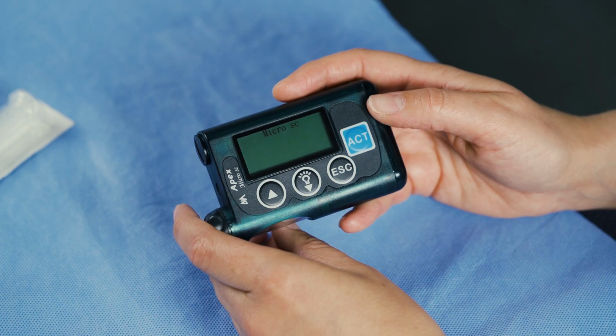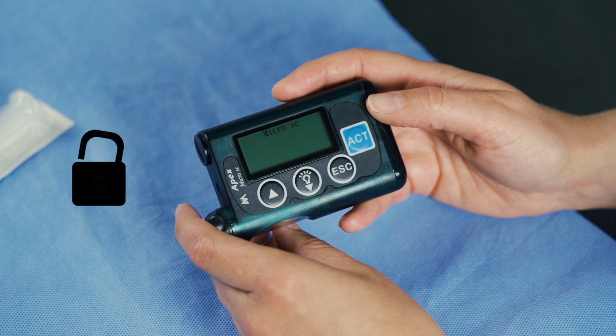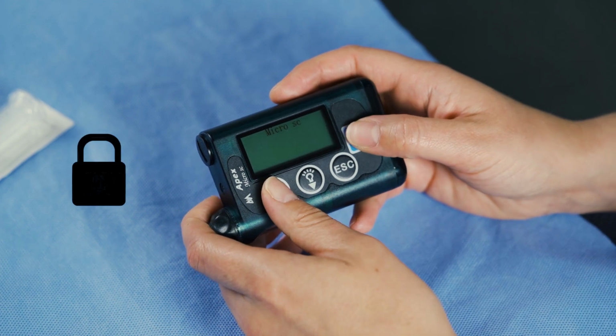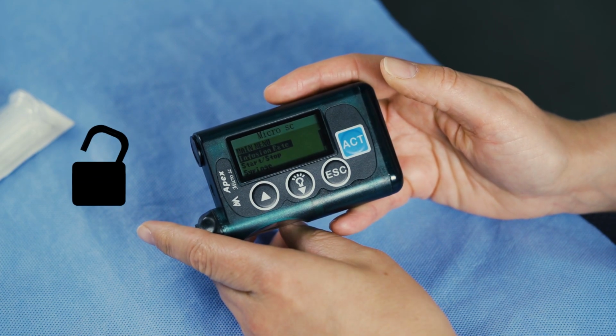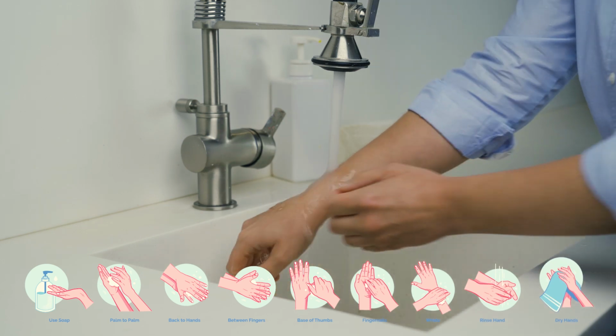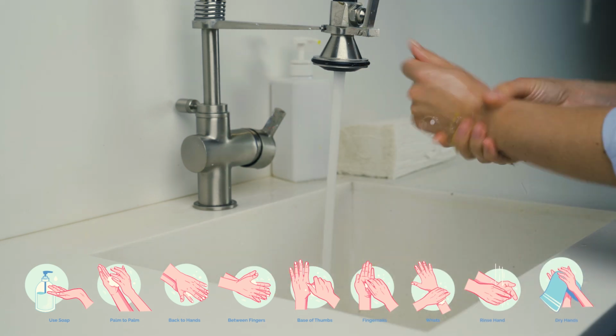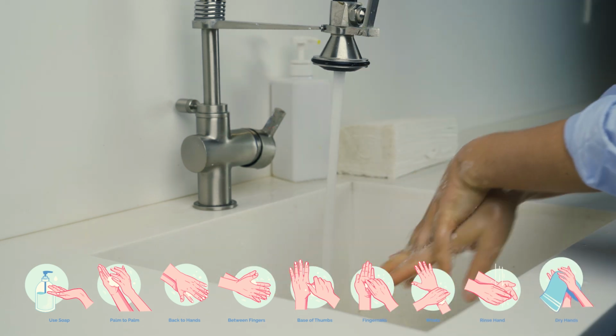For your safety, the Micro SC infusion pump screen locks automatically in 30 seconds. You can lock or unlock it by pressing the up arrow, then act buttons. A lock icon will be displayed on your screen, or an open lock icon will be displayed, and then the main menu will appear. Before you start preparing the infusion site and the pump, make sure that your hands are washed as illustrated here.